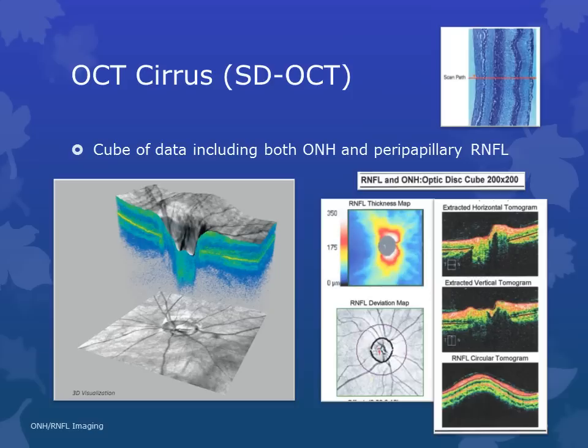The Cirrus OCT is the Zeiss machine which uses spectral domain technology — the one with higher resolution, faster scanning, and which gives more data. Unlike the Stratus where the scans are linear, the Cirrus OCT provides an entire cube of data. There is a test called the 200 by 200 cube: 200 A scans along one axis and another 200 A scans along the other axis — 200 times 200 equals 40,000 A scans covering the entire area.